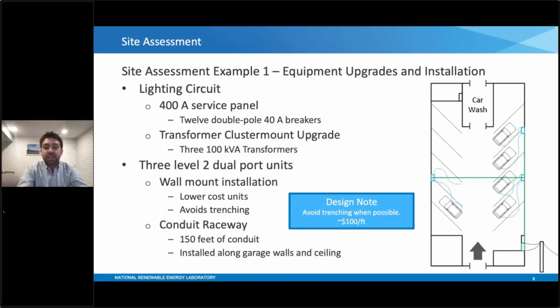That doesn't even include the costs of conduit and wiring, as well as the EVSE unit itself. So it's definitely important to scope out how far all of this conduit will need to go and how much wire you'll be requiring. But thankfully, trenching costs in this instance won't be too much of a concern, because we have wall mount units where that won't be an issue. We have it mapped out here, though. We have about 150 feet of conduit that will be required, and 150 feet or so of different wiring, most likely a 3-wire system, that will be going to each of these EVSE units.